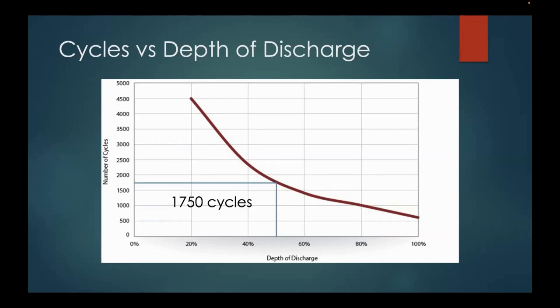Okay, so less than 5 years. If you cycle it to only 50% every day, you'll get 4.79 years out of that battery, and then you get to buy another one. Now, you could argue, well Greg, I'm doing grid-tied battery backup, my grid only goes down once or twice a year, maybe for 2 hours. Well, now you're looking at 15 years for this battery bank. So there's a lot of things we have to talk about.